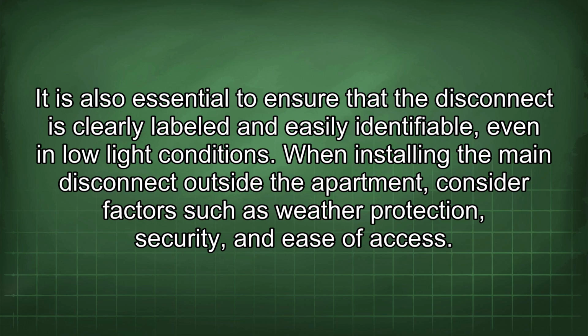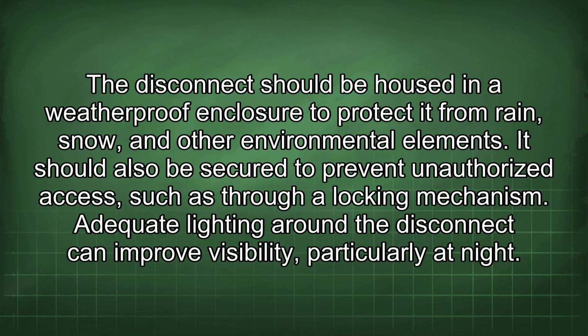When installing the main disconnect outside the apartment, consider factors such as weather protection, security, and ease of access. The disconnect should be housed in a weatherproof enclosure to protect it from rain, snow, and other environmental elements. It should also be secured to prevent unauthorized access, such as through a locking mechanism. Adequate lighting around the disconnect can improve visibility, particularly at night.